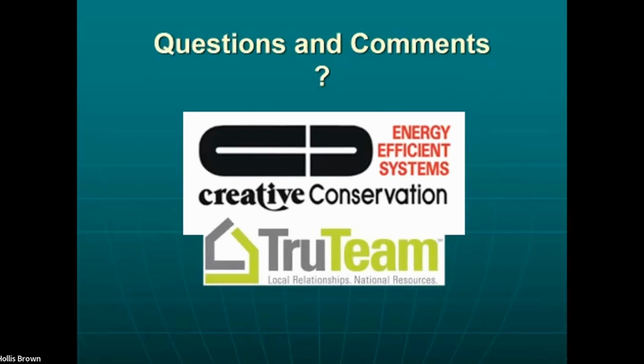Absolutely. And the other thing was, do you recommend that they shrink the size of their air conditioning system for their house after you do their crawl space and attic? No. Well, you're going to have an awfully big air conditioning system in there. It's not going to pull the moisture out right. Again, you and I could argue all day long whether that unit's going to short cycle. In new construction, we've definitely seen it happen. They will design a house for a certain tonnage, foam the thing from the ground up, and then the unit short cycles. Absolutely, no question about it. In an existing home, we haven't seen that happen and don't believe it will. House still leaks plenty.